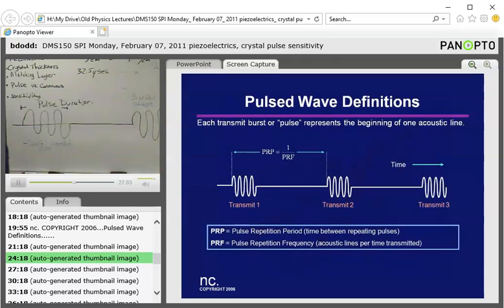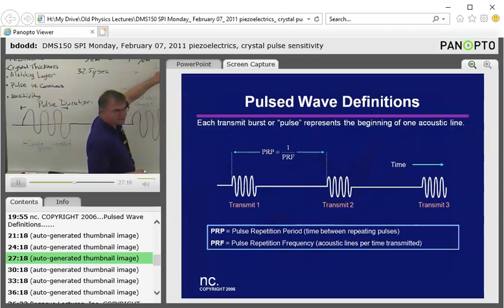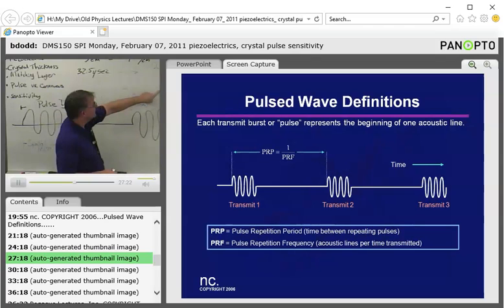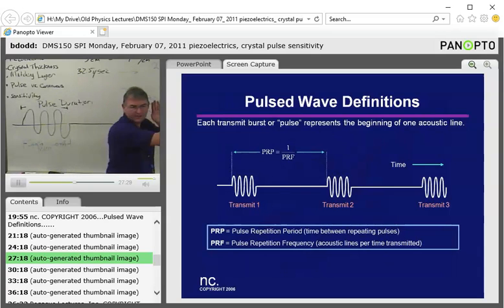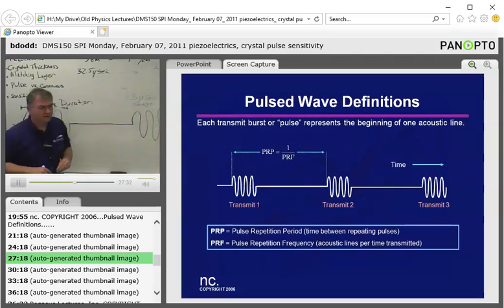And what we call the period of time that we're waiting to send out another pulse is called the PRP, or the pulse repetition period. Okay? And so to image 20 centimeters deep, I need a pulse repetition period of at least 260 microseconds. I have to listen that long before sending out another pulse. Okay? So if I send out a pulse along aisle 1 here, and I want it to get all the way back to Diana in the back there, I have to wait 260 microseconds for the pulse to come back to me.